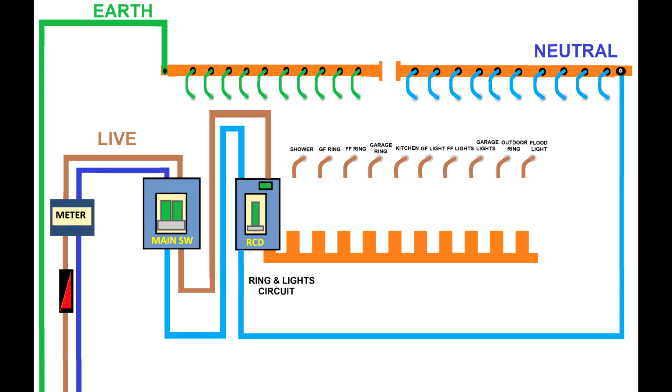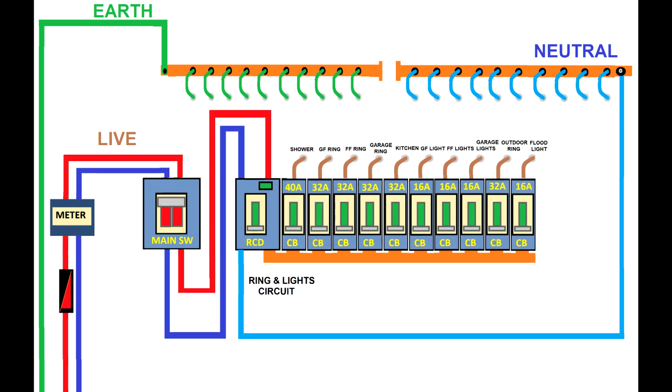So imagine if you use only one RCD, the RCD will provide power to the bus bar, and onto that bus bar you'll put circuit breakers. Each circuit breaker will have the capability to protect each individual circuit for an overload. So the circuit breaker is not a residual current device. Many people are confused when the residual current device trips. They say my circuit breaker tripped, the big one. Everybody tells me it's the big circuit breaker. It is an RCD, a residual current device, which protects you against fire and any other electrical hazards.